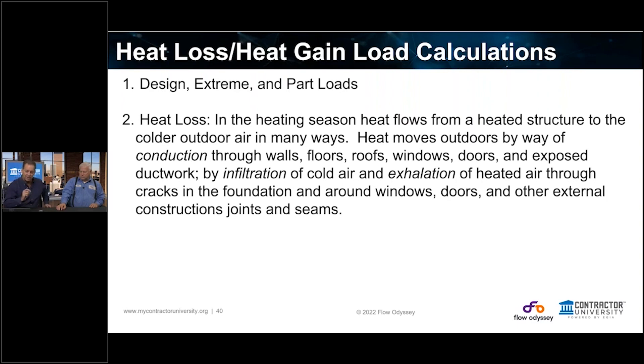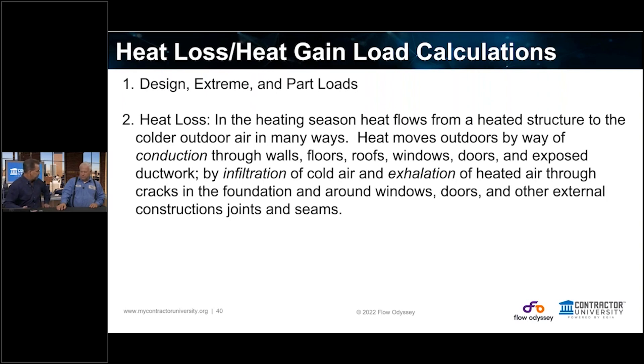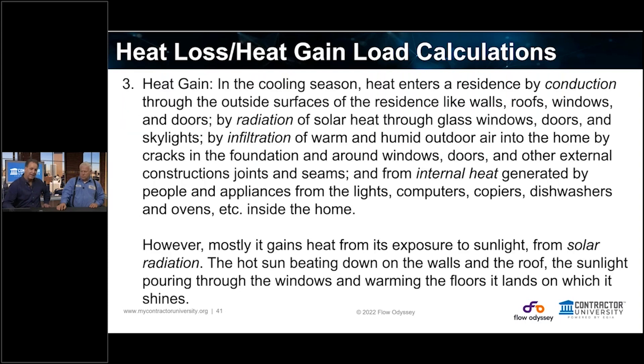In a heating season, the heat flows from the heated structure — hot wants to go to cold. Heat moves by conduction through walls, floors, roofs, windows, doors, and exposed ductwork, and also by infiltration of cold air. The rate at which heat loss occurs increases the lower the temperature goes. On the heat gain side, the hotter it gets outside, the faster heat wants to come inside the house — lower pressure and temperature inside. The hotter it gets, the harder your air conditioner has to work. Most homeowners don't understand this; they just go to the magic box on the wall.